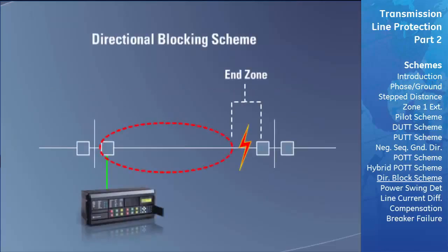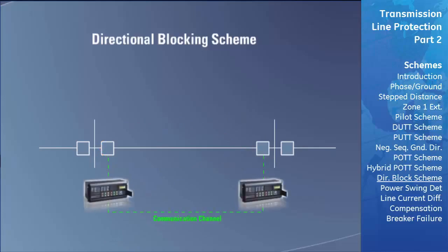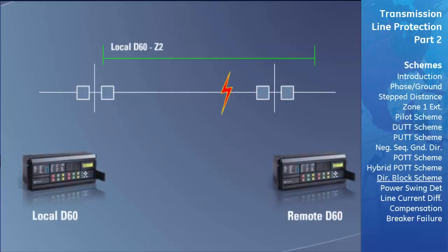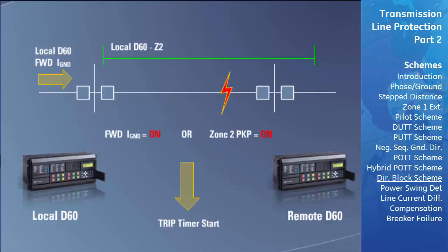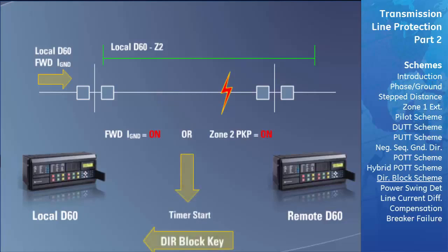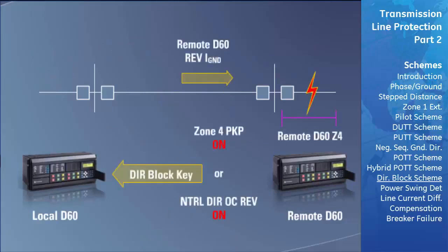The directional blocking scheme is one of the most popular teleprotection schemes used in distance applications today. Its purpose is to speed up tripping of faults in the end zone of a transmission line. The local relay has an additional delay timer started by detecting either a Zone 2 fault or forward ground current. This timer is set considerably shorter than the normal Zone 2 delay. When it expires, the local relay trips unless it receives a block message from the remote relay. The remote relay only sends this blocking key if it detects a fault in its Zone 4 or reverse-flowing ground current, both indicating an external fault.